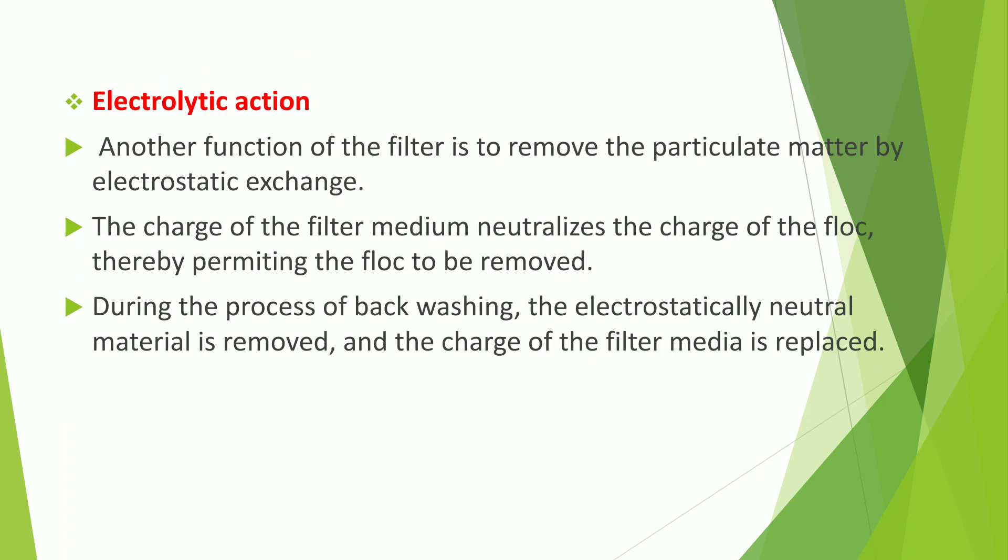The last action is electrolytic action. Another function of the filter is to remove particulate matter by electrostatic exchange. The charges present in the impurities are removed through electrolytic action taking place in the filter media. The charge of the filter medium neutralizes the charge of the floc, thereby permitting the floc to be removed. During backwashing, which will be explained later, the electrostatically neutral material is removed and the charge of the filter media is replaced.